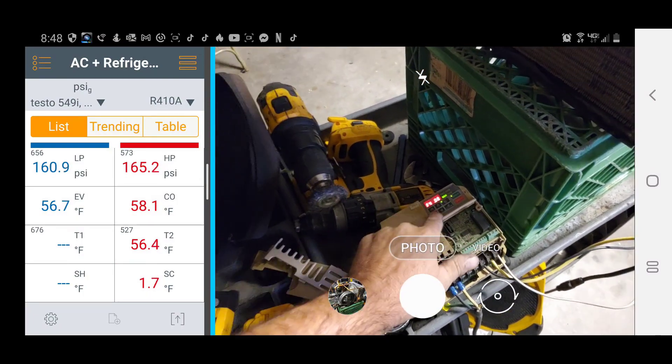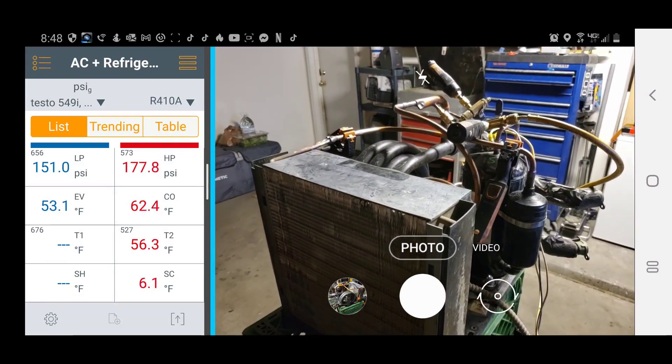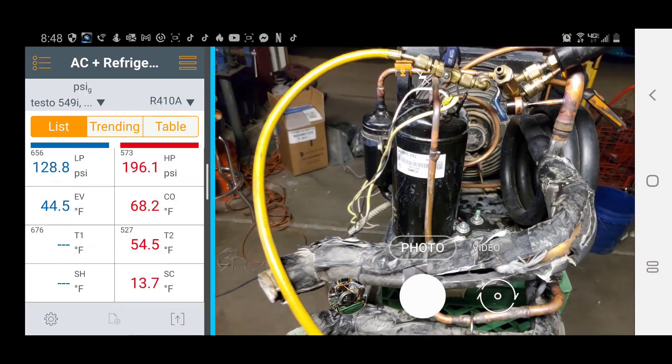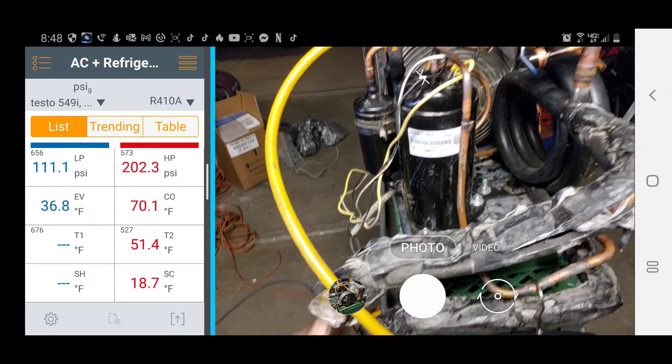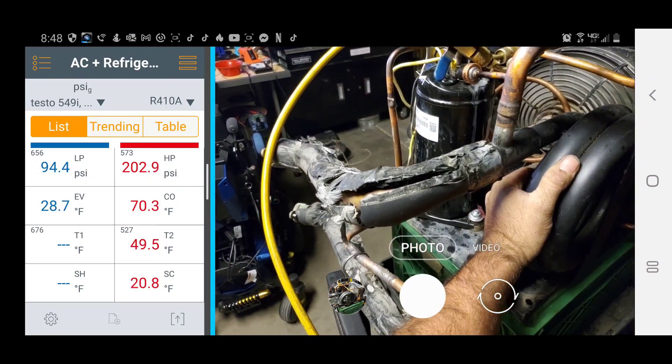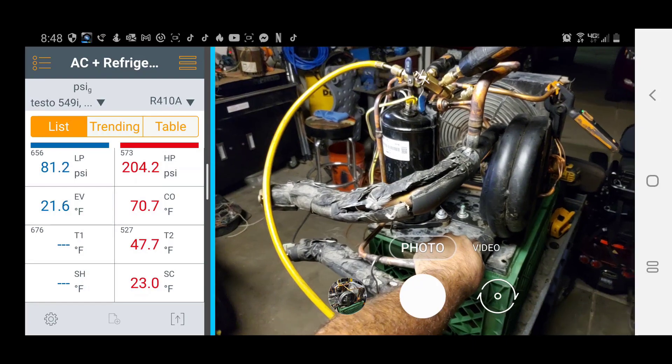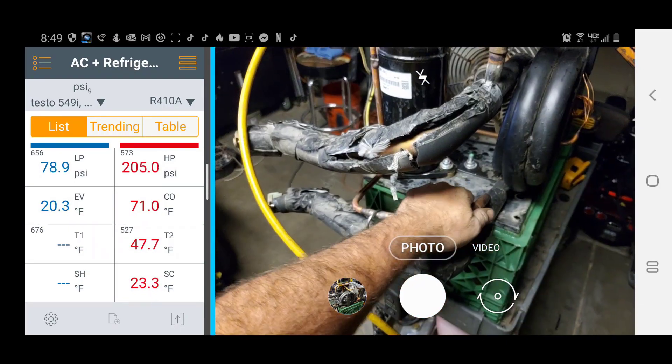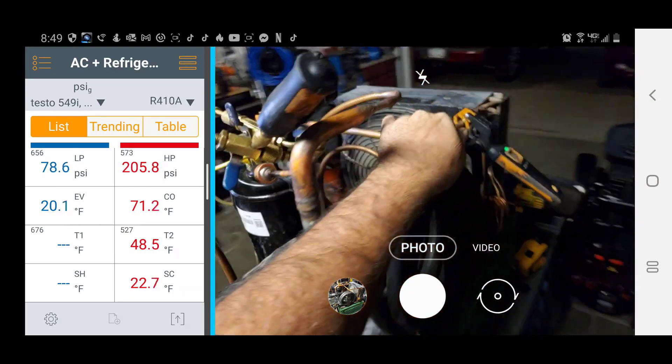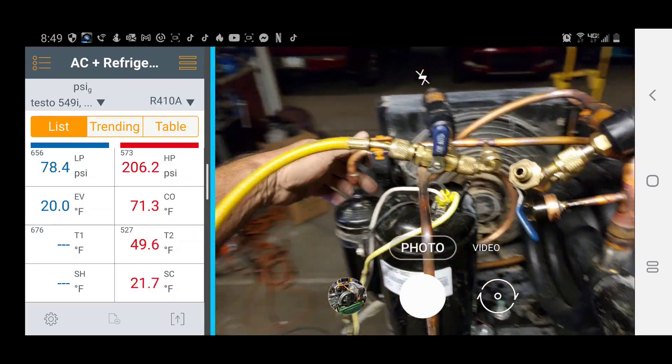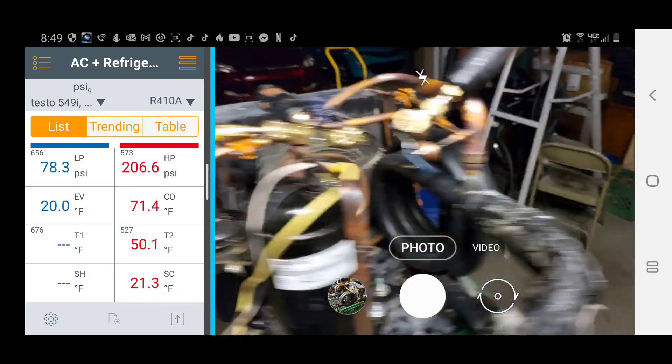I'm gonna try running it one more time before I take this out of screen capture mode and see. The pressure is on the screen. The refrigerant charge is just a ballpark. You can see the high side never shoots up that much, although there's a bit of subcooling. Oh, and I don't even have water feeding through this thing, so I expect the high side to start climbing, and it isn't. This is warm but not hot. And maybe it actually just needs—well, I'm saying it needs more, but look at the subcooling, it's pretty high there. Oh, that would be—I moved the wrong meter, that's why. I moved the meter onto the wrong thing. I thought that was the liquid line.